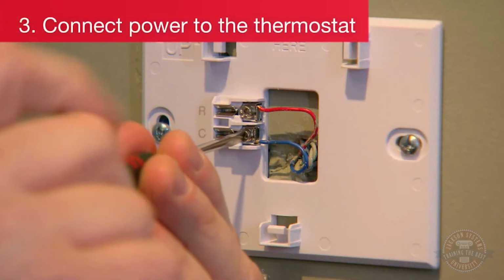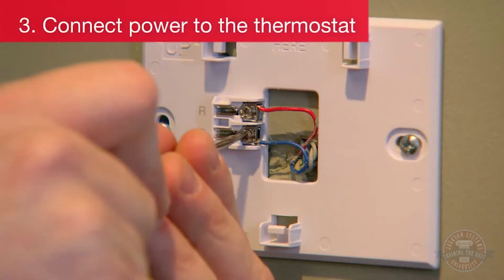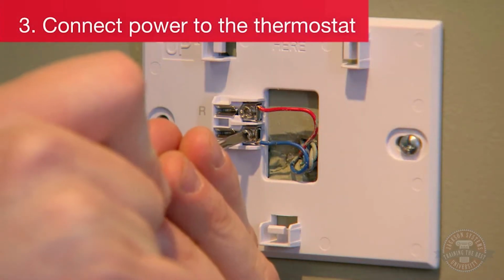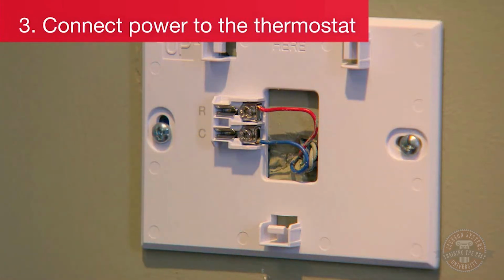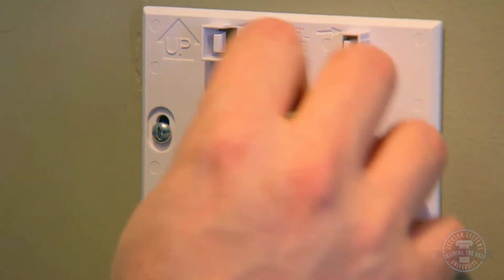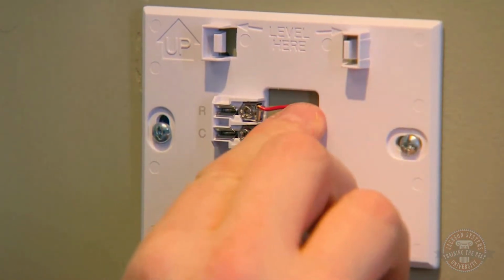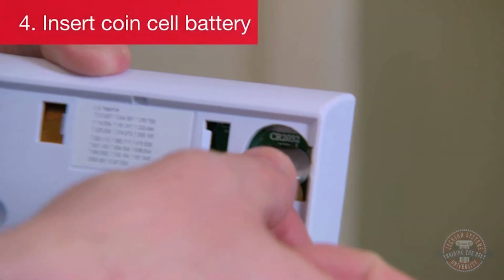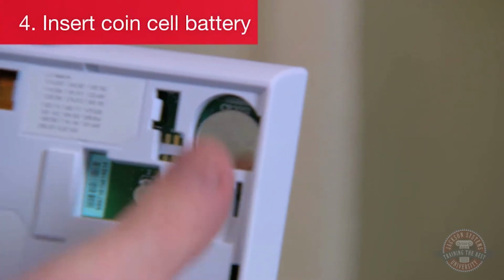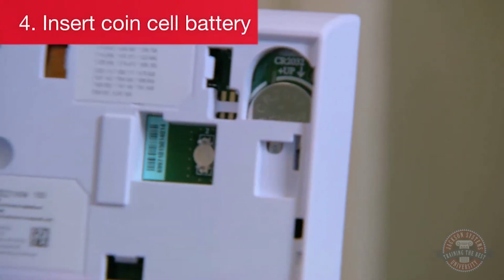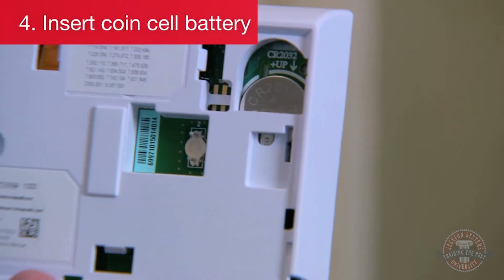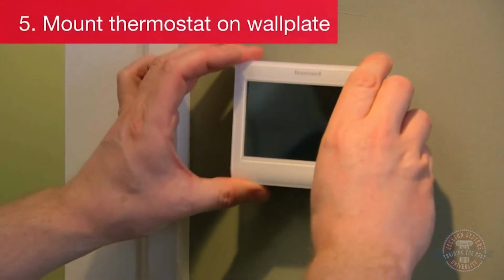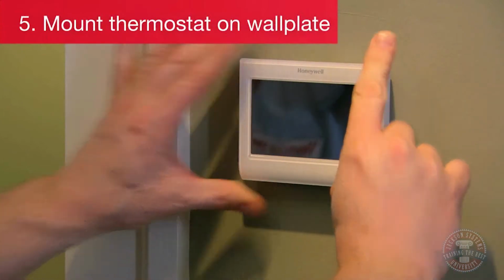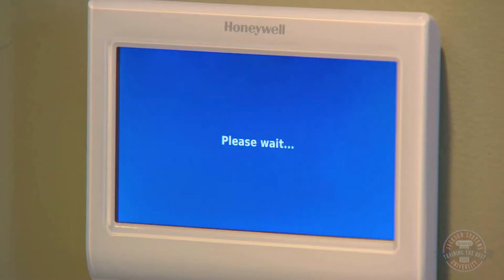Next, connect power and common from the EIM to the R and C terminals at the thermostat. You can also use a separate 24-volt transformer to power the thermostat. Push excess wire back into the wall opening once it's connected. Then place the coin cell battery in the thermostat as shown with the plus side up. The battery saves time and date in the event of a power loss. Finally, align the thermostat to the wall plate and snap into place. System power can now be reapplied.